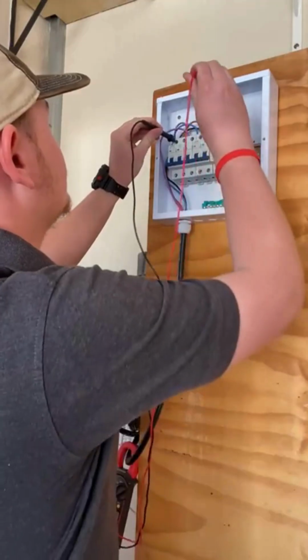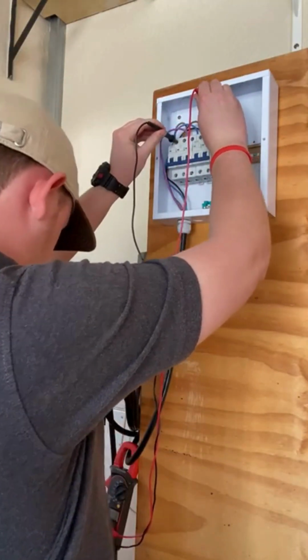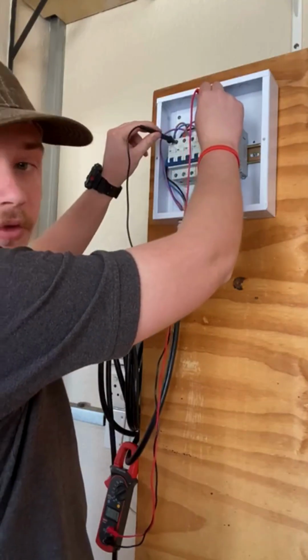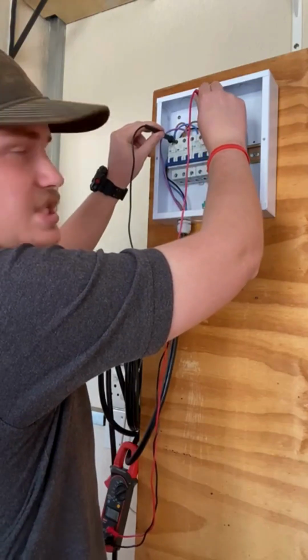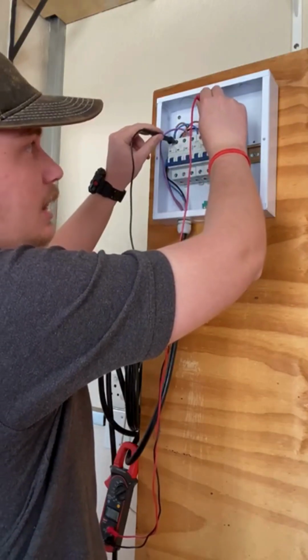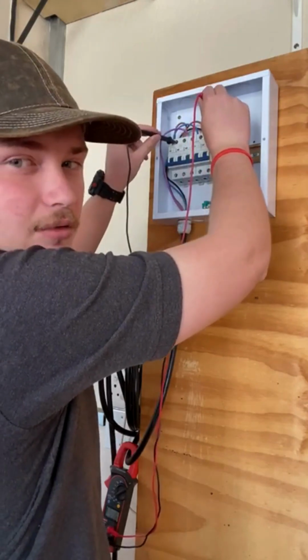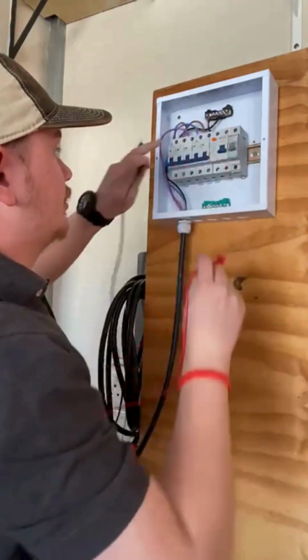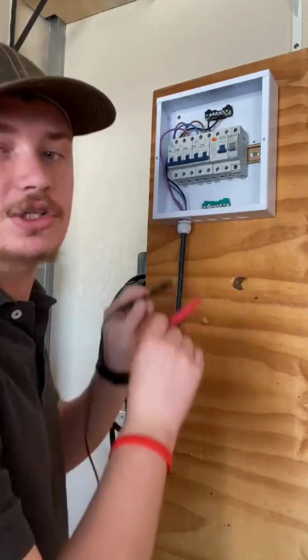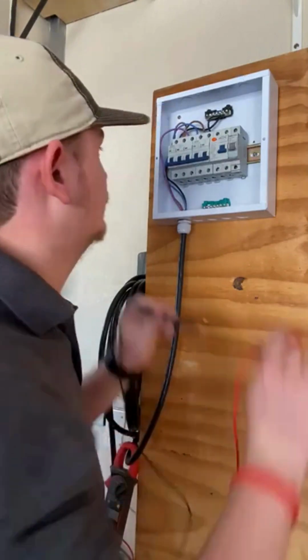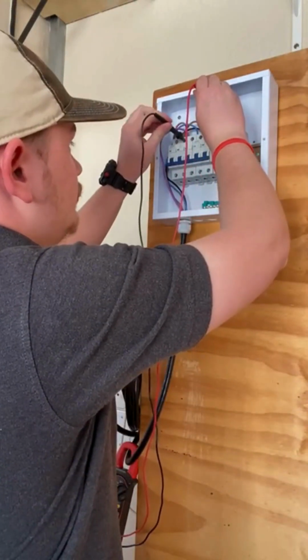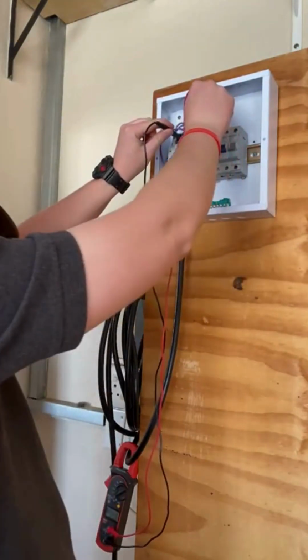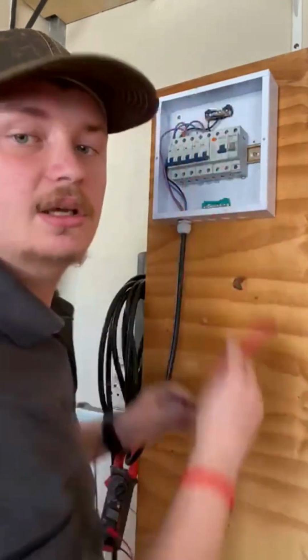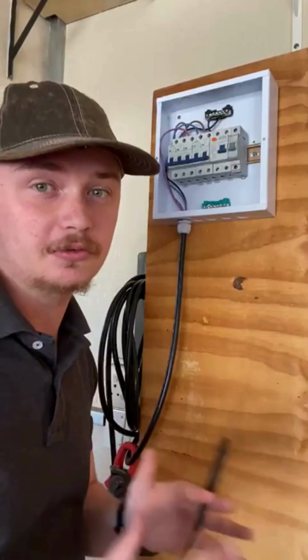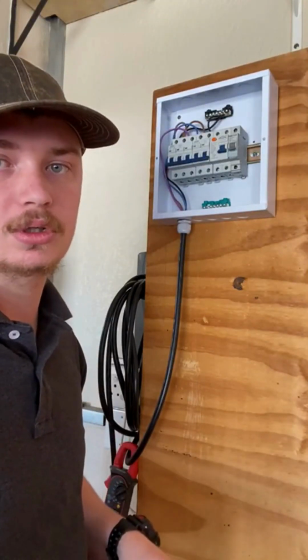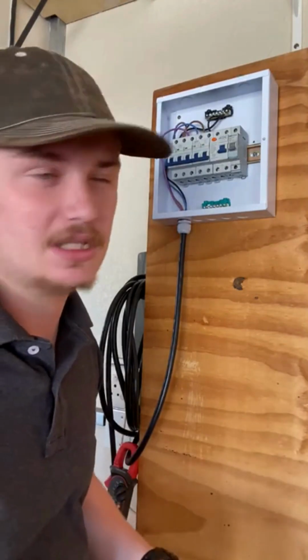So from L1 to neutral, we are getting 235 volts, which is in spec because that's like single phase stuff - even though I'm measuring it on the 3-phase isolator, one phase to neutral will be about 230 volts. If we do the same with L2, we're getting 239, again in the spec of that 230 to 240 range, which is normal for one live to neutral.